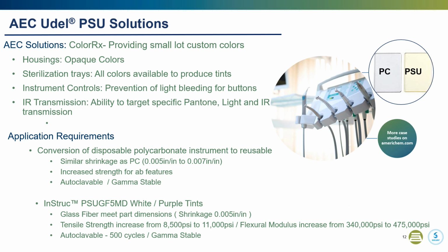Our application here is a reusable version of an existing disposable polycarbonate surgical tool in transparent colors. The requirements included maintaining similar shrinkage as the polycarbonate, increased strength and flex modulus, and being able to survive 100 steam autoclave cycles. We came up with 5% glass-filled PSU. The 5% glass helped to meet the critical dimensions by lowering the shrink from a range of 5 to 7 thousandths inch per inch to a more consistent 5 thousandths inch per inch, and also improving mechanical properties.